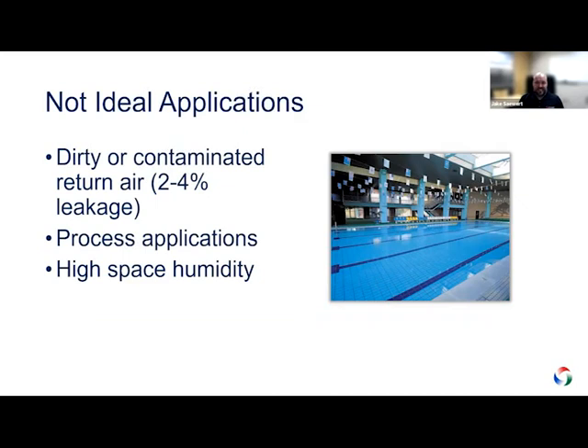There are some places where this is not intended to be used. It does have cross-contamination like an enthalpy wheel would. It's because when it's flipping the dampers, you're going to have air lost in that section, and it'll flow the other way. So it's about 2 to 4%. Because of that, it doesn't make sense to be using this for any type of dirty or contaminated air. Process applications are not good. Anything like a pool that has a high level of humidity in the space, again, not a good application, just because you're going to have so much moisture that's actually going to be trying to get put back into the airstream on the supply side. It just doesn't make sense.